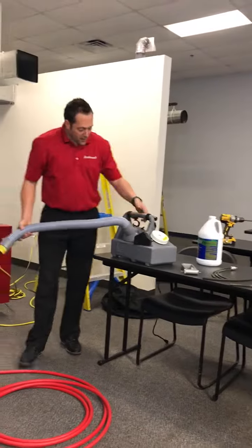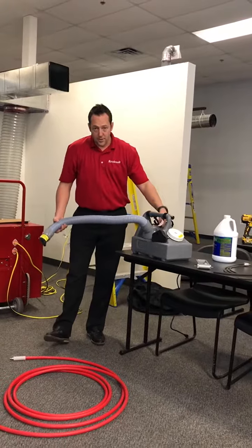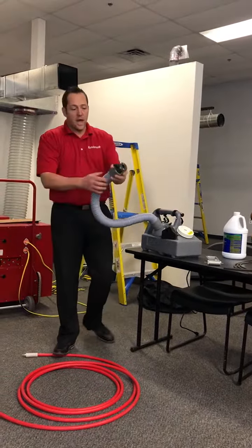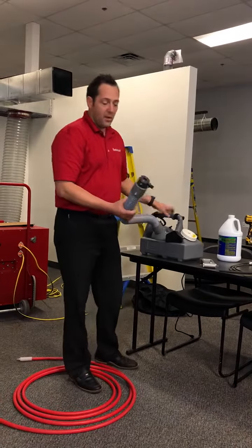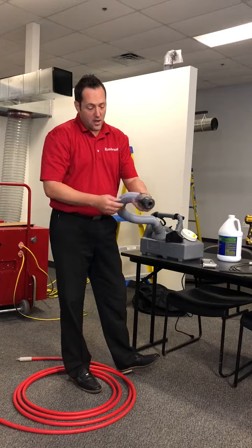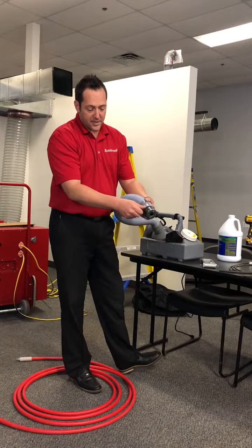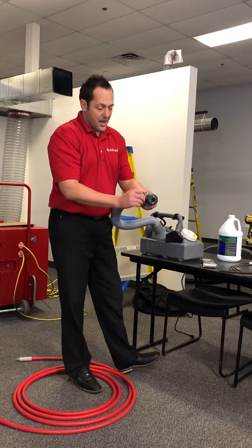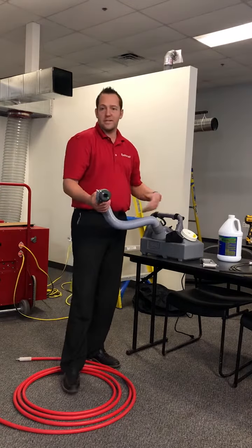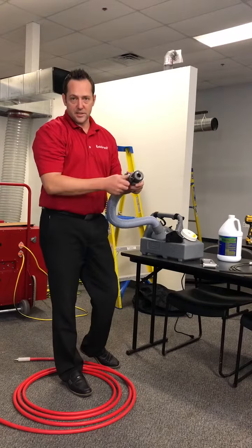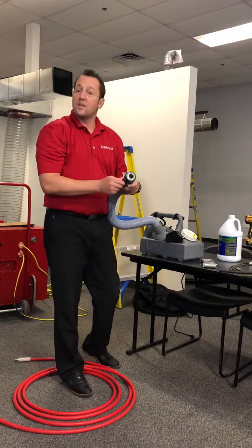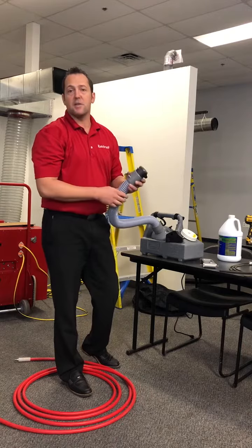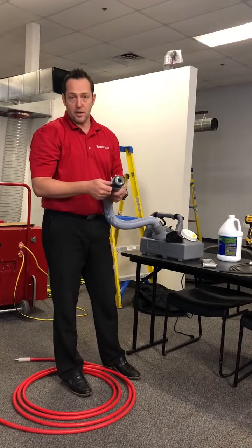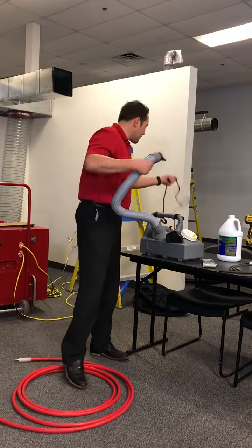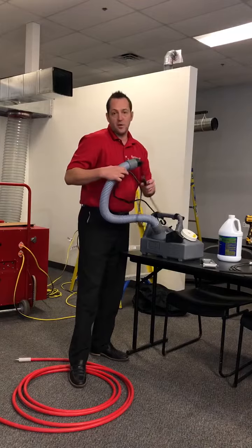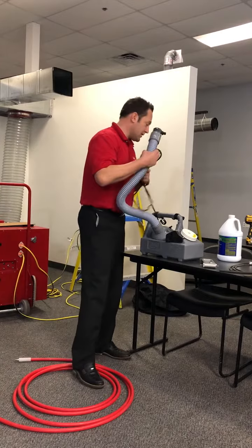Now, on the fogger itself, you have an on and off switch right there on the top. So that'll either turn it on or off. Now the line itself, while the fogger's on, is blowing air directly through the nozzle. On the side, you have a knob; you just rotate it to the amount of mist that you want coming out. The fogger will take the chemical that's in there, atomize it, basically turn it into a mist, and then you'll fog the system itself. A rule of thumb is you don't want the ductwork saturated. So again, 60 seconds per 1,000 square feet is what you're looking for. Do not saturate the ducts. It is a 110, so you just plug it directly into a 110 outlet.